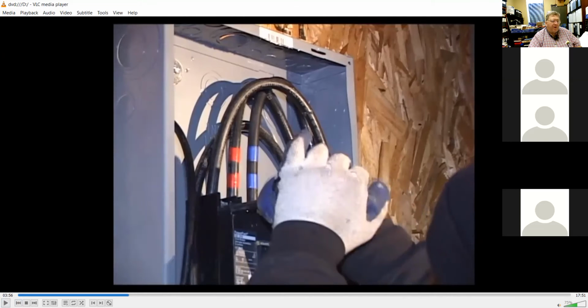Now, I'll add something to that. We use lockout devices. They make lockout devices that can go directly on a breaker. If you see them in my webcam, you see that breaker there. They make lockout devices that go directly on the individual breaker, so that you can lock out the individual branch circuit. We're a little tighter on it than just simply flipping it off and then going at it. I'll show you those devices when you're up here on campus. We have a variety of lockout devices.